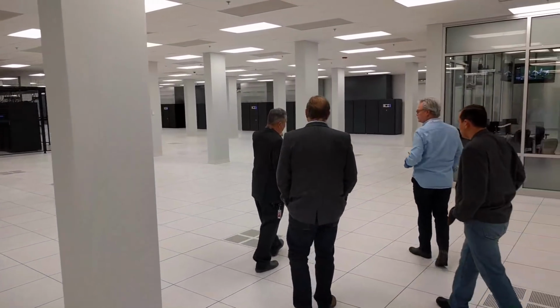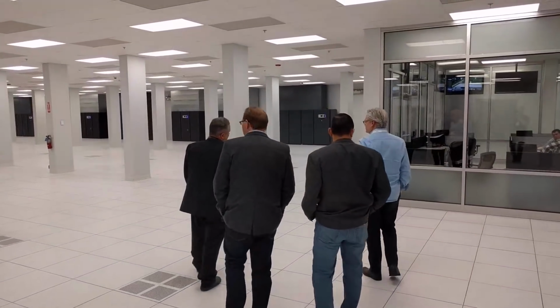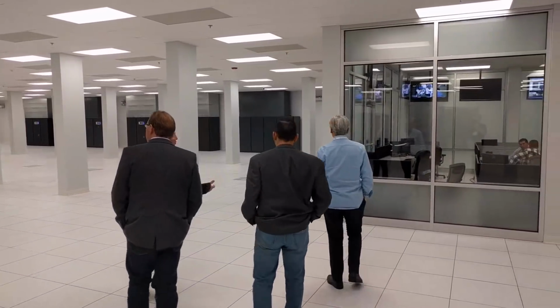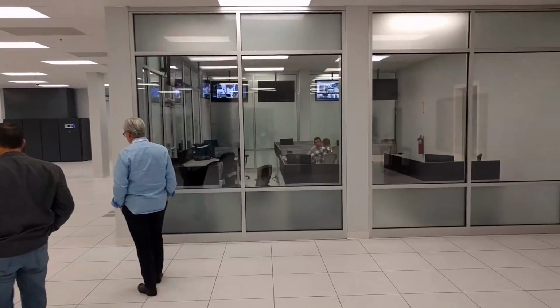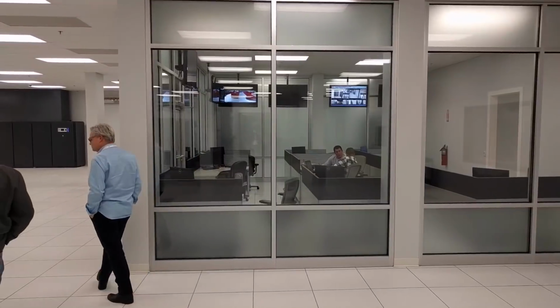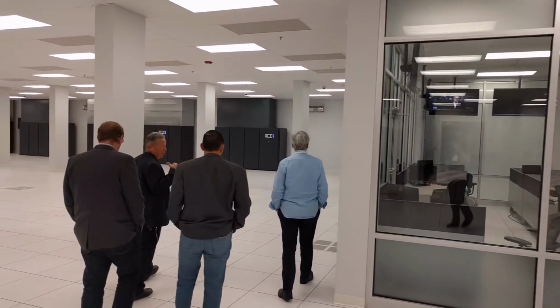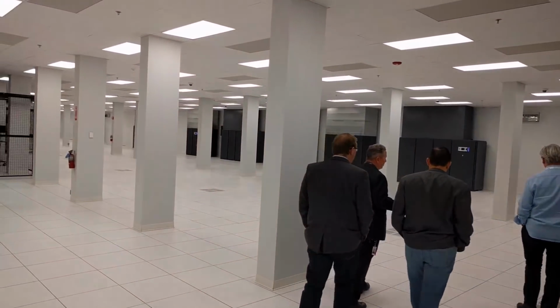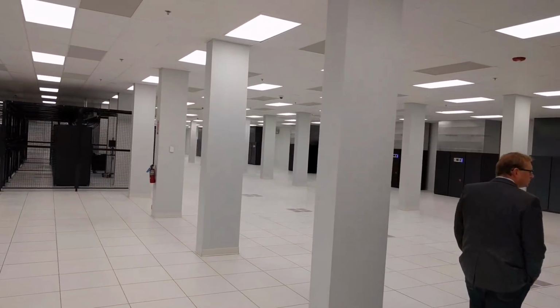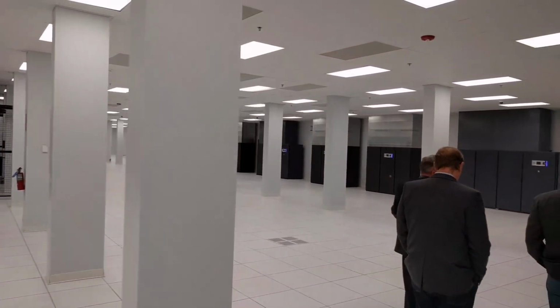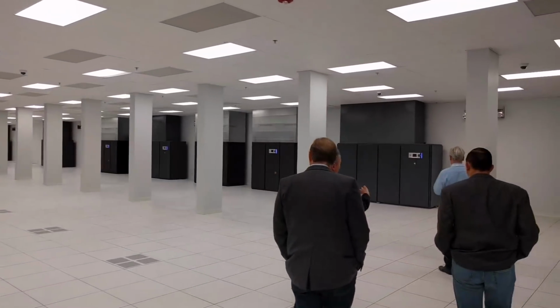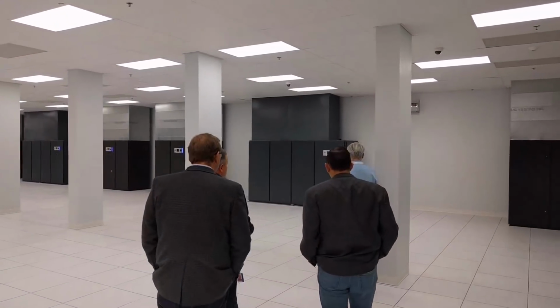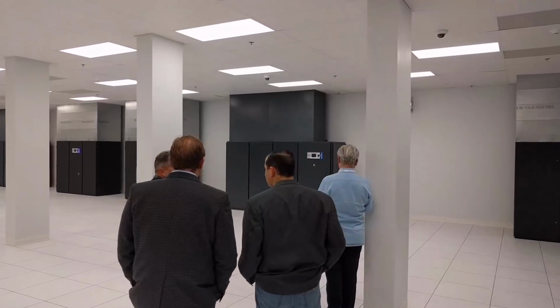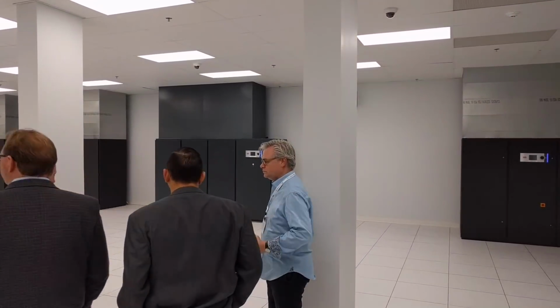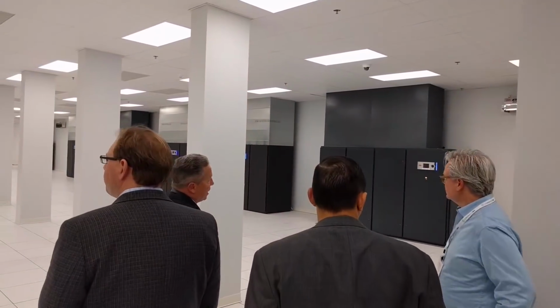These are all 30-ton air conditioning units. Some are self-contained, and some are on a dual 300-ton chiller plant. The ones with silver tops are air handlers, connected to our chiller plant where the cold water is made. These units are independent of each other and the chiller plant—each has its own dual compressors, its own refrigerant, its own glycol loop, its own dual pump package, and triple fans. So there's redundancy upon redundancy in here.